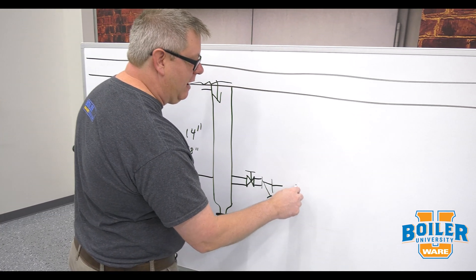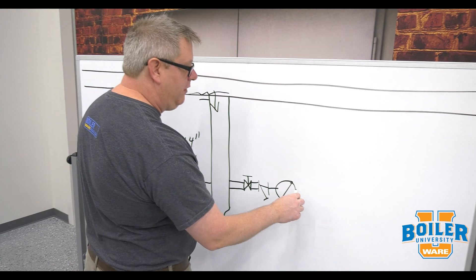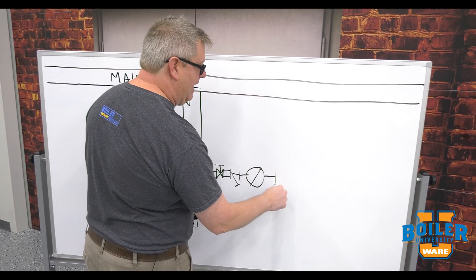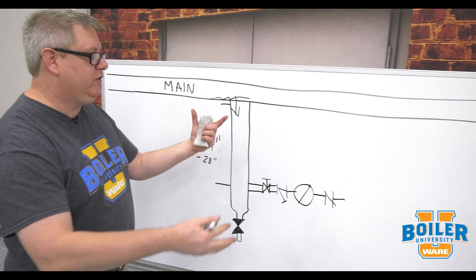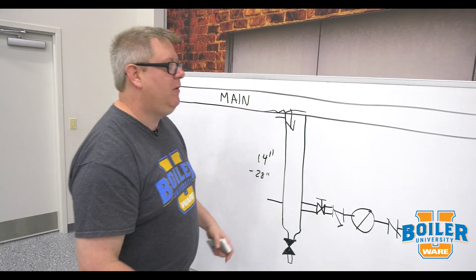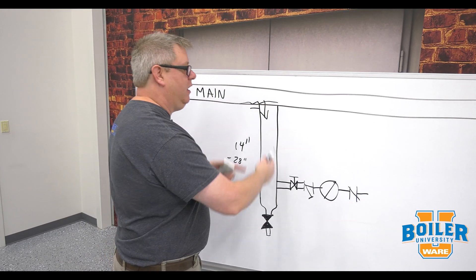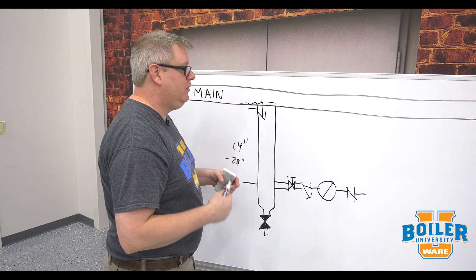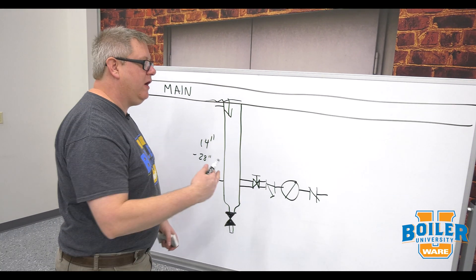Then we're going to have our trap itself and this is just a generic icon for a trap. On the outlet of the trap we're going to have a check valve and the benefit of a check valve on the outlet of a trap is when the system's shutting down there's no way for the vacuum in the steam system to suck condensate back into the header.